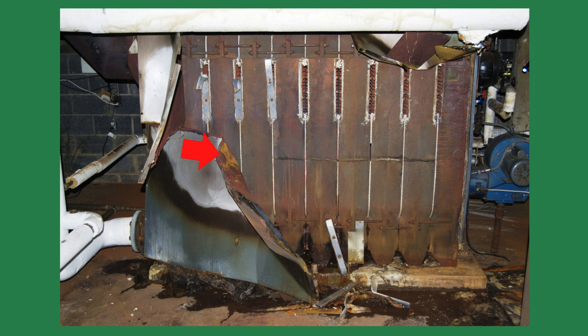The firefighters used their metal saws to cut the boiler jacket to gain access to the flame. They trained their hoses on the hot boiler and opened a valve. One firefighter shut off the main gas valve, feeding the building. When the fire was out, they discovered the boiler sections were cracked. They were lucky, as spraying cold water on a boiler usually results in an explosion. This one didn't.